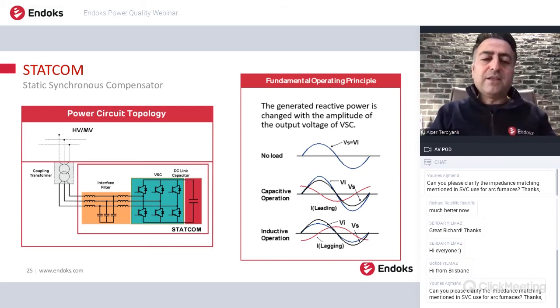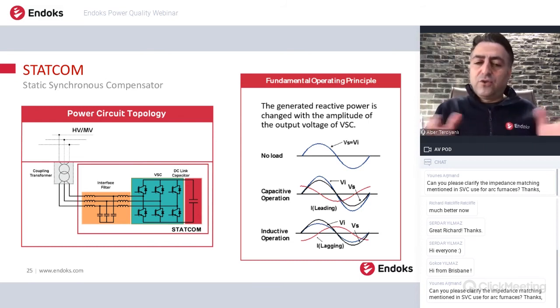Hence, this current is circulating on the STATCOM itself. Hence, we don't need any additional external power source for STATCOM. STATCOM can operate independently. The capacitor on the DC link is being used in order to maintain the DC voltage, because we have a DC, we have a converter, and we are using this DC voltage to create AC on the AC side. But this DC capacitor does not require any additional external source to supply any reactive power. So we don't store any reactive power. The reactive power is just flowing through the grid and the STATCOM itself. We only need a little amount of active power, for the active power losses of the converter itself.